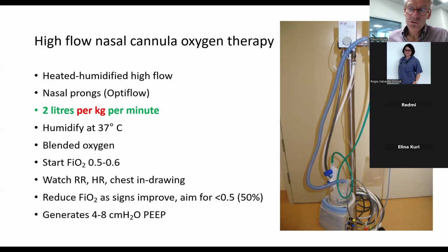And this is a crucial part of the way high flow works. It needs to be blended and it needs to be humidified. And so this is the humidifier down here, and that's usually set at 37 degrees. And there needs to be a source of gas flow, which here is the oxygen flow, and that could be through a cylinder or even potentially through a concentrator. There needs to be a source of gas flow, both airflow and oxygen flow. And there needs to be some nasal prongs.